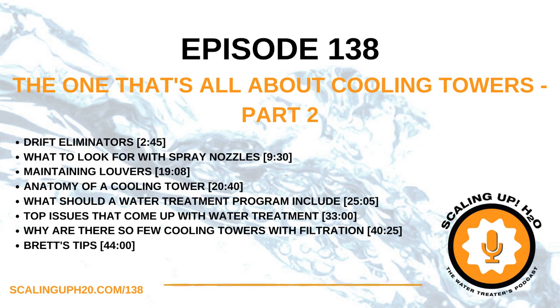Now, if somebody has an older counterflow tower, can they refit it with the newer design drift eliminators? Yes, they can. So that's a huge talking point and somewhere that water treaters can even add value, because you're out there every month looking at the tower, hopefully doing a walk around and inspection. Every so often you could even go up or talk to the operator and say, hey, we should go up and inspect the drift eliminators and make sure they're there, and two, that they're not damaged. And then what year were they manufactured? What are the drift rates?